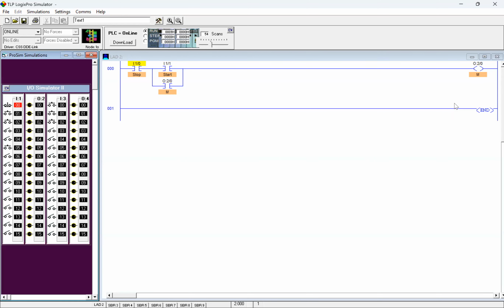So when you do that, you have to wire through the overload into a normally closed contact, which is buried on the overload. And you have to get in there and wire from the back side of your coil to that, out and back to the neutral or whatever you're using, if it's 0 or if you're 24.